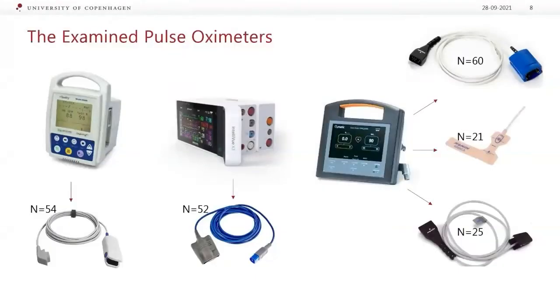For a better understanding, I will just show you the pulse oximeters and probes that we have investigated. First, we have Criticare, where we did 54 observations. Then we have Philips with 52 observations. And then we examined 3 Nonin probes used with automatic. We had 60 observations with the blue finger probe, 21 with the disposable probe, and 25 with the ear probe.